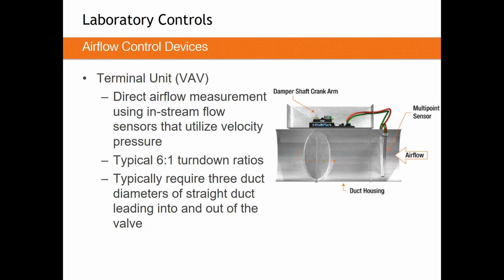The VAV box, however, was never asked or intended or designed to be the most accurate device in the world. They were originally intended and are still used today to be airflow and temperature and comfort control devices, really. So they can measure airflow and they can do an okay job of it, but they're not going to be claiming an accuracy of 2 or 3 or 5% accuracy, really in any sort of range. You may be able to take a VAV box and balance it at a certain constant volume airflow and make it a fairly accurate device. But as soon as you try to get some turn down out of a device like this, your accuracy is kind of going to fall off and away.